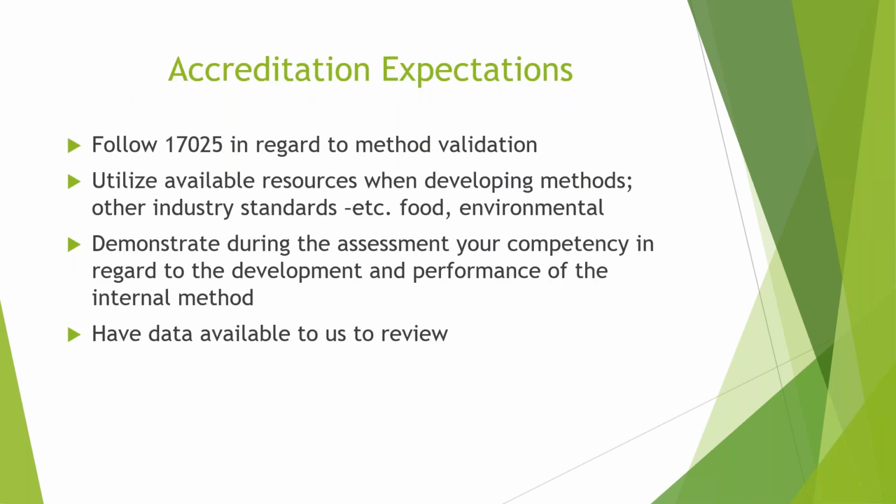So just our expectation is, one, we want you to meet the 17025 requirements in regard to method validation. There's multiple ways you can validate a method. There's available resources that you could obtain from different industry groups, or potentially start with a method that's already been in place for several years, potentially in the food, maybe environmental industry, and utilize that as a baseline.